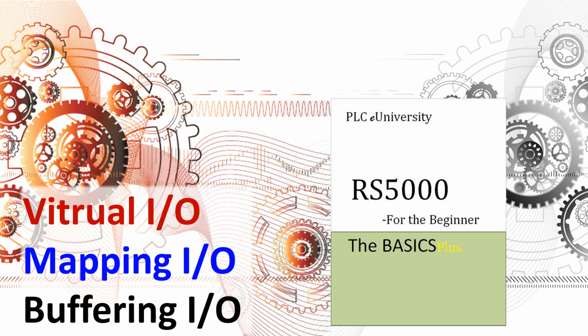For that reason, there is a problem in writing a program where in your first rung or your first couple rungs, you look at the state of an input and then make a decision, and by the time you get to the end of the program, you're assuming that decision is still good, where in fact the conditions in that rung earlier in the program have now changed, and had you executed that logic again, you would get a different result.